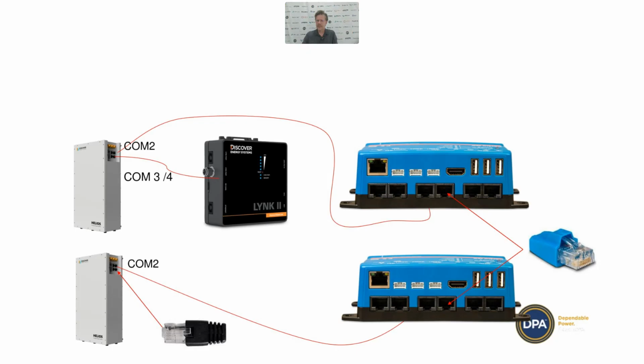Well, if you have AC coupled solar and no grid, they would need to be on the output of the inverter, because there will be no AC voltage on the input side of the inverter if the grid is down. It will vary the charge current according to values it's reading on the AC side, and it will throttle any AC coupled inverters with frequency in order to prevent itself from overcharging the batteries.